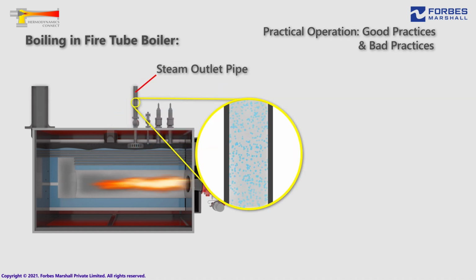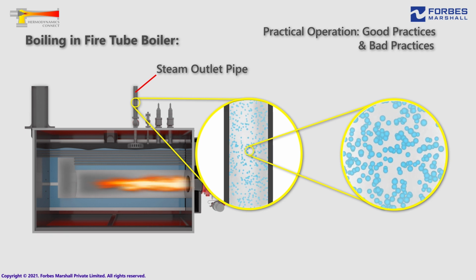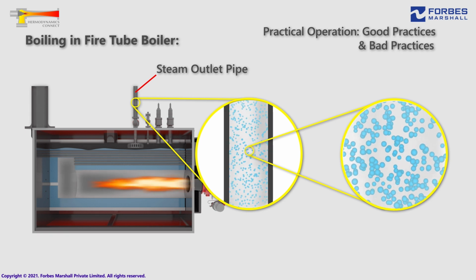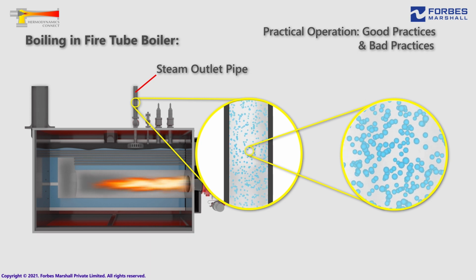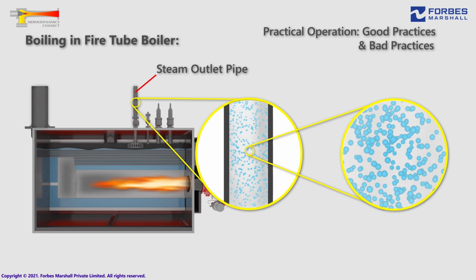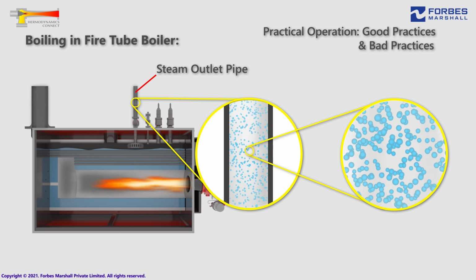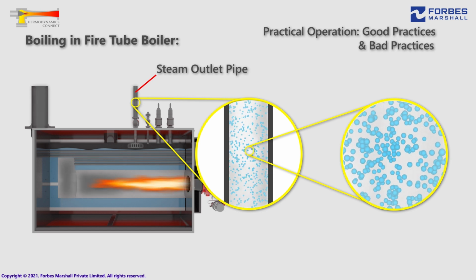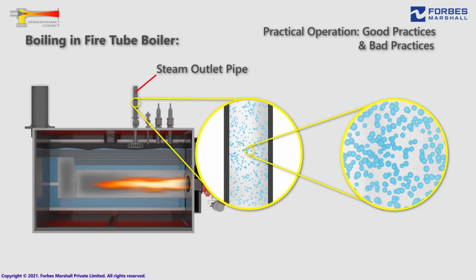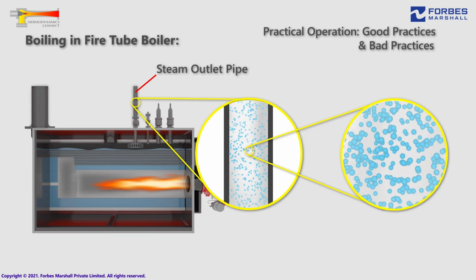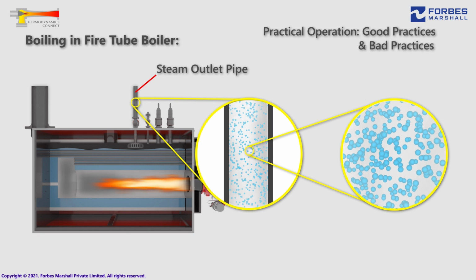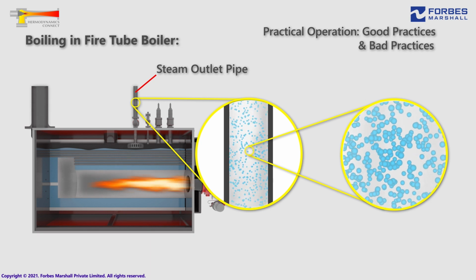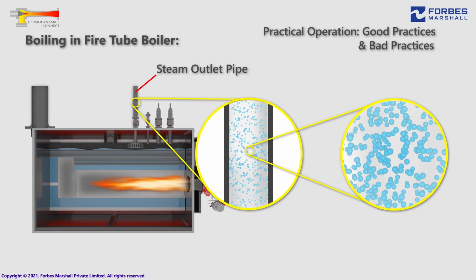Lastly, the presence of such invasive layers also reduces the dryness fraction of steam that the boiler can generate. This means there is more moisture present in the outgoing steam, which reduces the specific heating value of steam going to a process. This in turn increases the steam demand for the process, further stressing the boiler, which is already operating at higher loads due to the deteriorating effects of the scaling, etc.